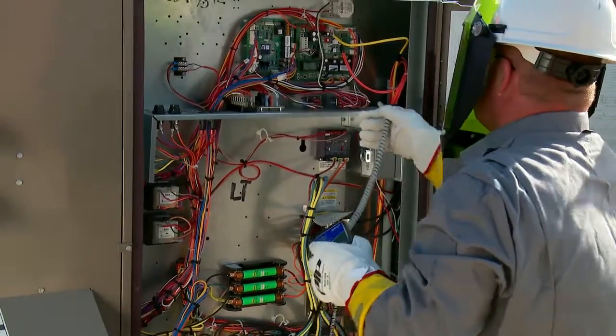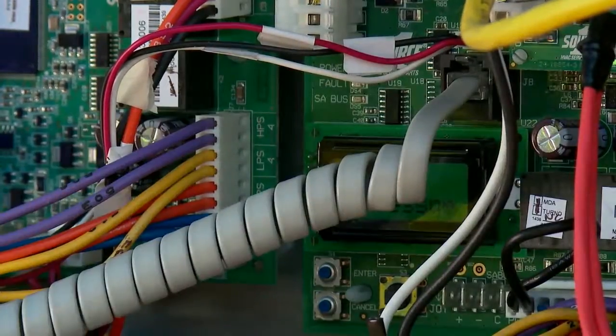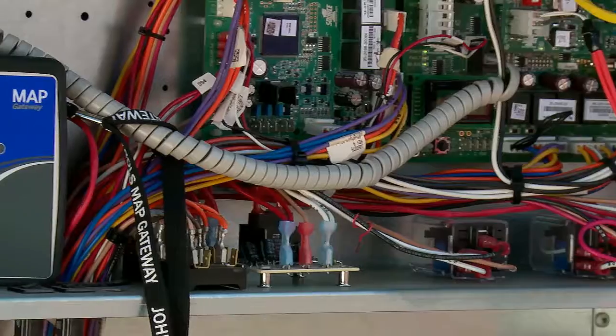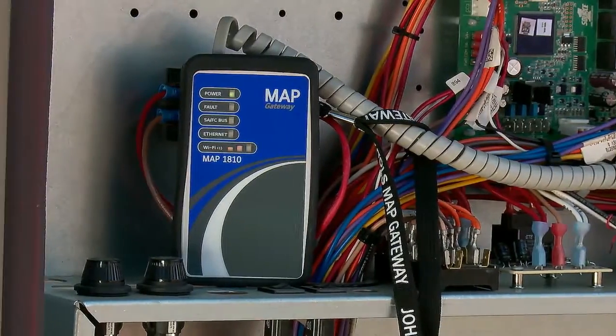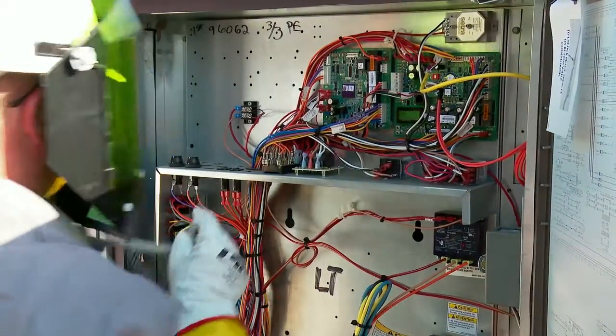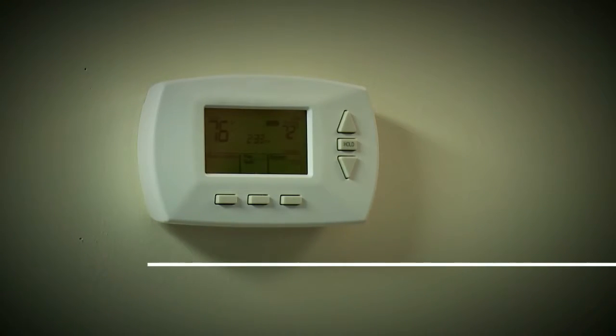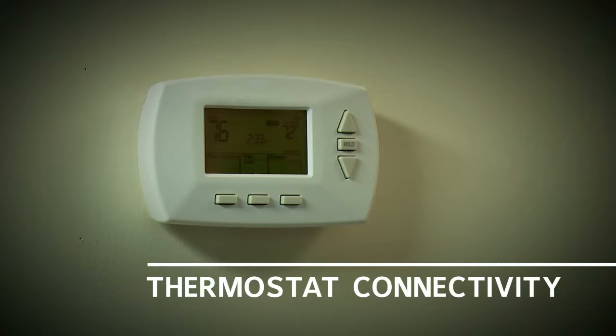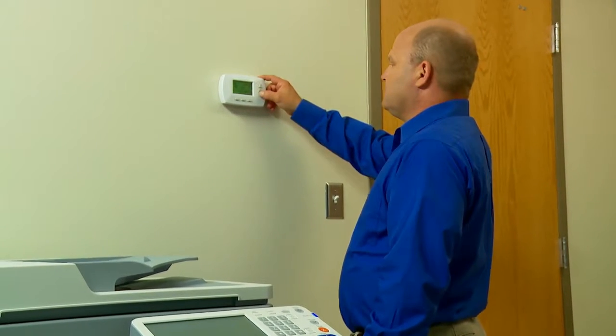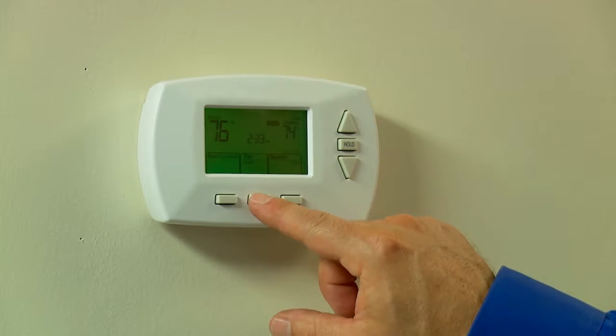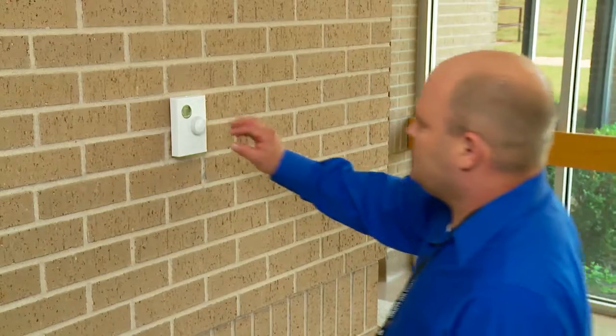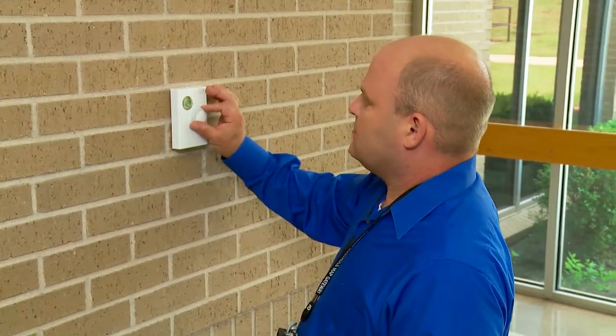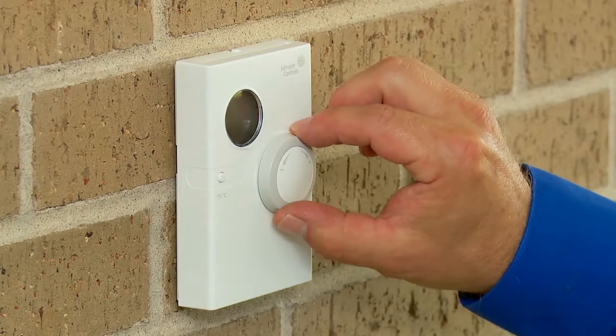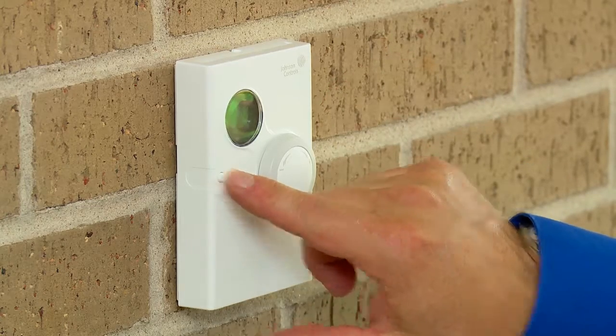Along with basic connectivity and readouts at the unit, SE Controls also make high-level communications and control easy by providing several flexible connectivity methods. One of the things we know, the majority of installations are done with thermostats. So the SE Controls supports connections with standard programmable wall-mounted thermostats. And of course, a Johnson Controls wall-mounted network sensor, which includes a display, override set point dial, and override button.